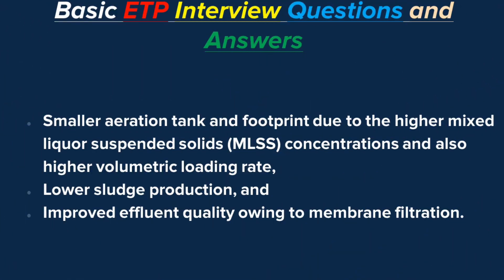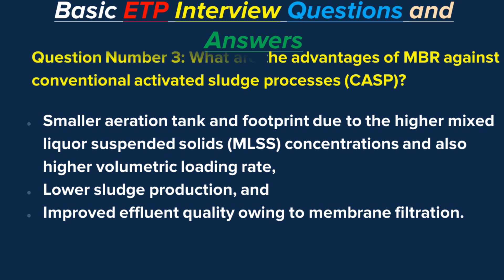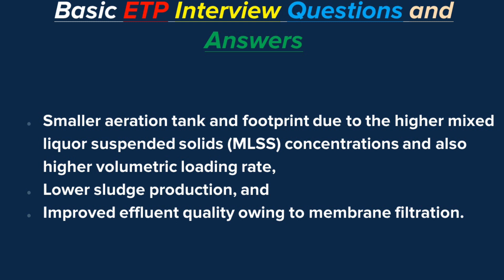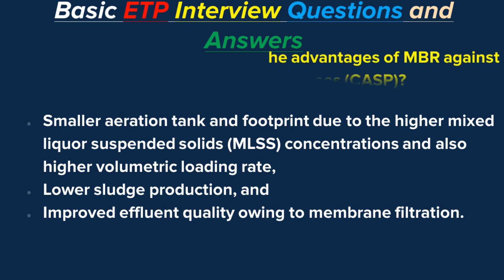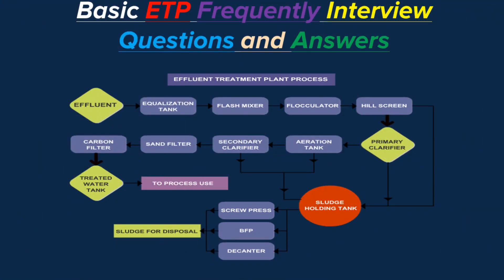The main advantages of MBR technology compared to conventional activated sludge process are: smaller aeration tank and footprint due to higher mixed liquor suspended solids (MLSS) concentrations and higher volumetric loading rate; lower sludge production; and improved effluent quality owing to membrane filtration.